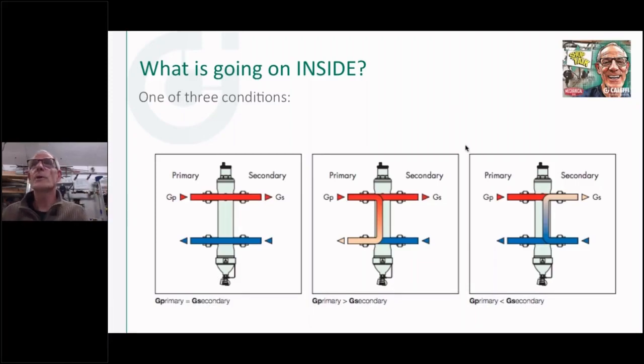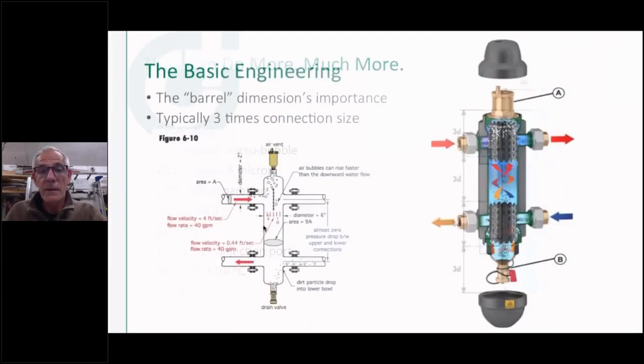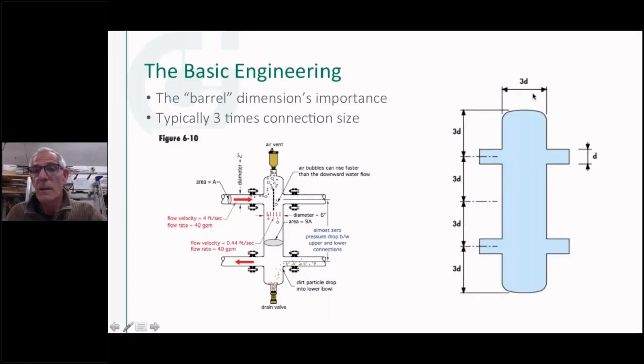So anything else while we're in the question category there? Let me look up. Stanley had a question here. It says 3 times the diameter of the boiler feed or the system feed. Am I right in thinking 3 times the largest diameter pipe? Yeah, 3 times. So let's say this is 2 inch, then this needs to be 3 times that pipe size that's coming into it. So this would need to be 6 inch.